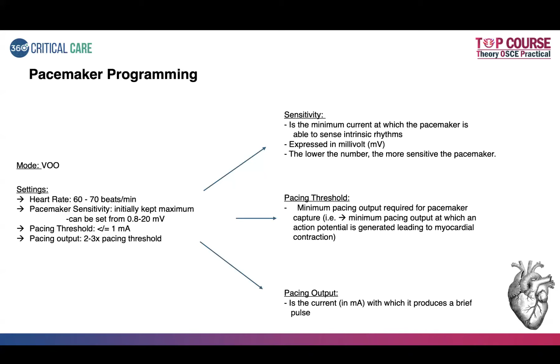Then you have the pacing output. The pacing output is the current with which it produces a brief pulse. From the pacing generator, the current is being delivered through the leads to the right ventricle. That is mainly determined by the pacing output. It is the current with which it produces a brief pulse. Intrinsically, that pulse is produced by the SA node. But in the event of bradyarrhythmias, there may be some kind of defect in your electrical pathways. So this transvenous pacing via the pulse generator takes care of that.